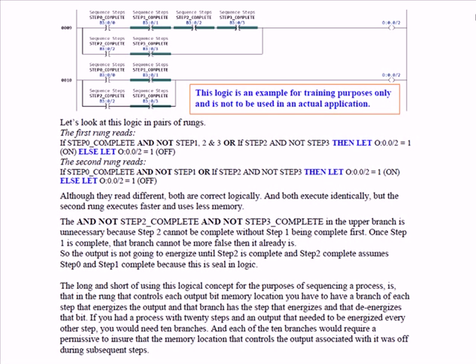If you had a process with 20 steps and an output that needed to be energized every other step, you would need 10 branches. And each of the 10 branches would require a permissive to ensure that the memory location that controls that output associated with it was off during any subsequent steps.